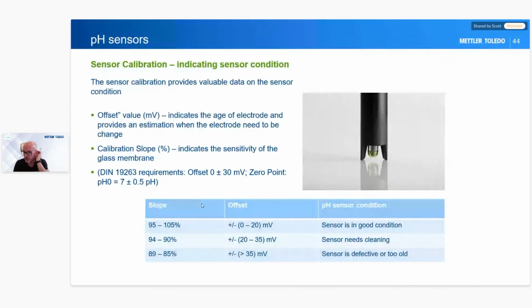It's really important that you understand, when you've taken a calibration, whether it's a good calibration or a bad calibration. Here we say the sensor's in good condition or bad condition. This is only correct if your pH buffers are correct. So now we're presuming that you've taken care of your buffers and you've got the right buffers.